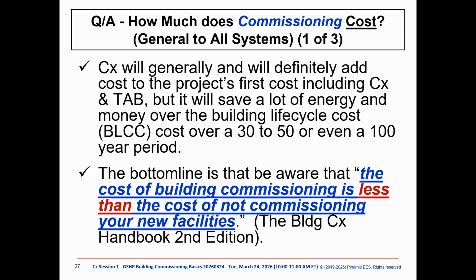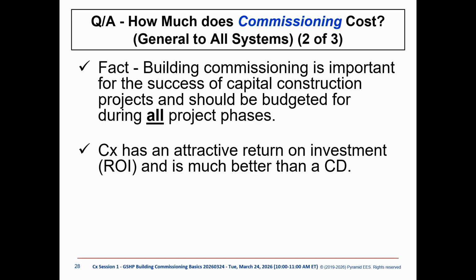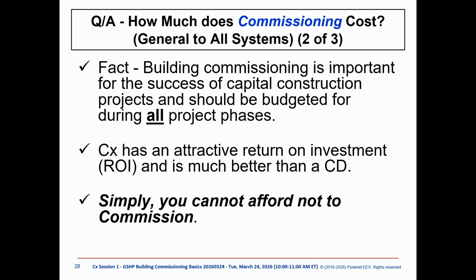The bottom line is that the cost of building commissioning is less than the cost of not commissioning a new or existing facility. So you save by commissioning. It's almost a free thing if you look at how much you save over the years. Building commissioning is important for the success of capital construction projects and should be budgeted for during all project phases. Commissioning has an attractive rate of return on investment, even better than a CD. Look at how much money you can save. Simply, you cannot afford not to commission.